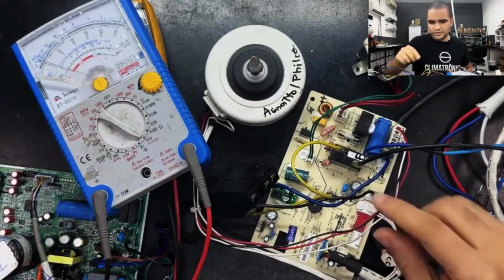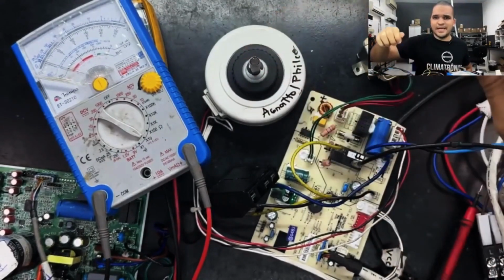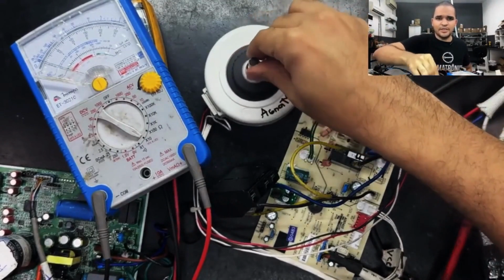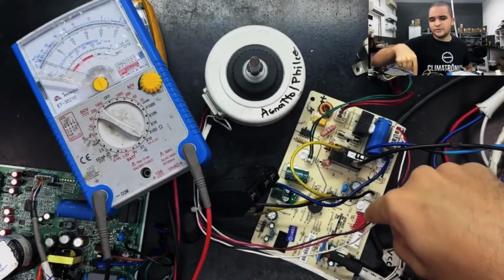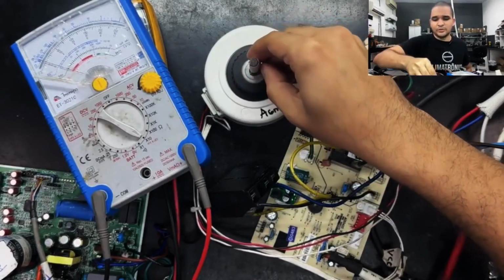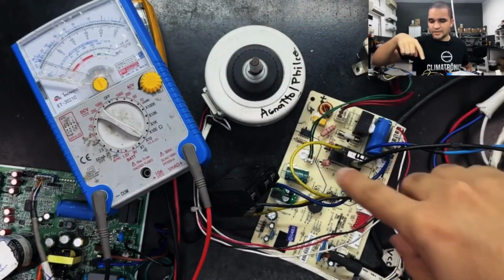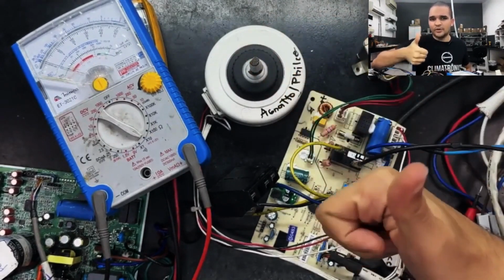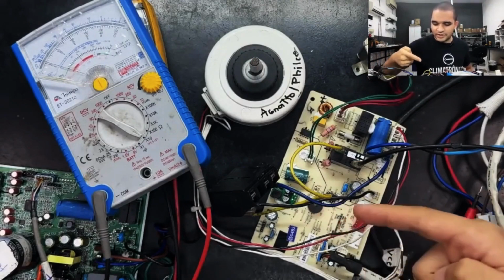You are already knowledgeable about whether the fan signal is functioning by simply powering the machine and manually rotating it while measuring the voltage at the pin. If the voltage at the pin changes, the motor is operating correctly. If it does not change, the motor is indeed faulty, correct?